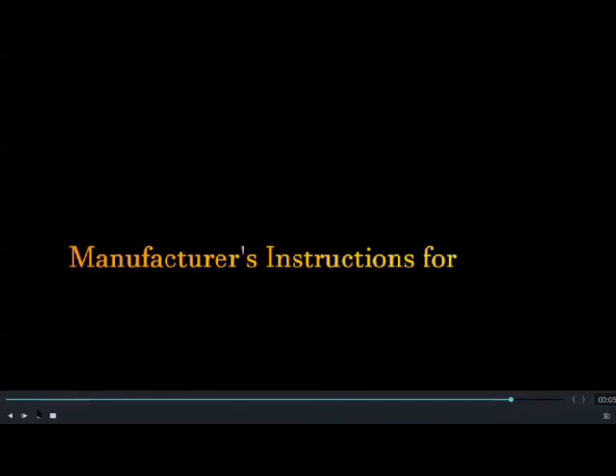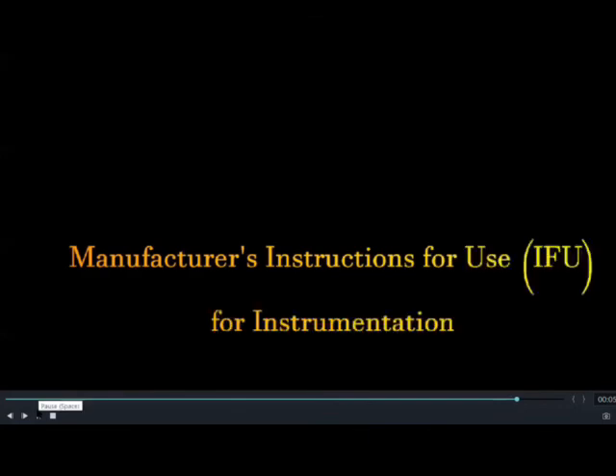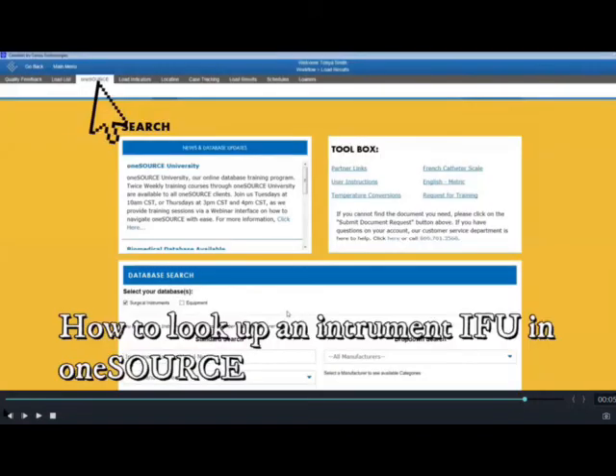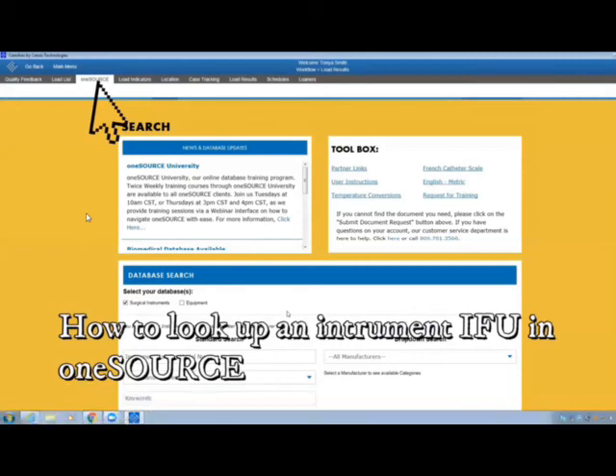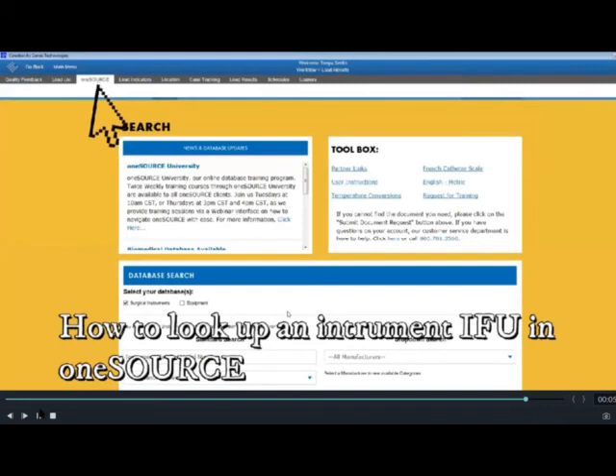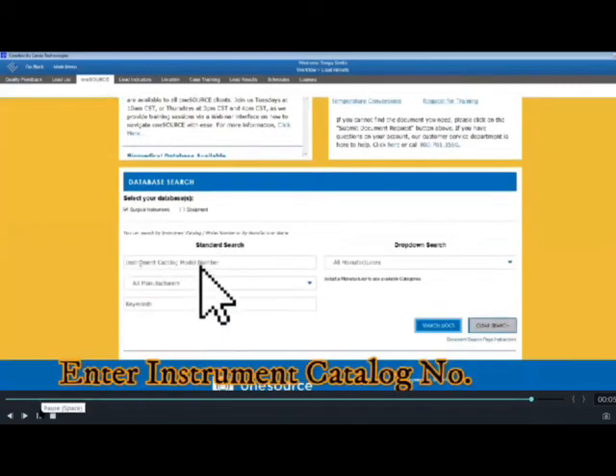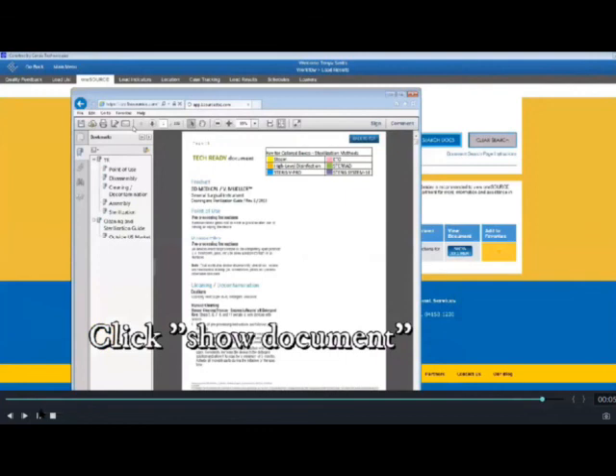So now we're going to look at checking the manufacturer's IFU, because that is part of the process. So, how to look up an instrument's IFU in OneSource. When you are within the CensiTrac system, you can go ahead and use the OneSource on the banner that it's pointing to, or you can go to our device and instrument page on our SharePoint. So in the search banner, you're going to put the instrument catalog number and click show documents or search documents. And then once you show the actual document, you can retrieve all of the information regarding that.